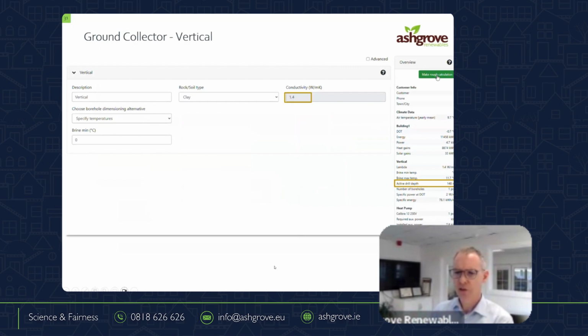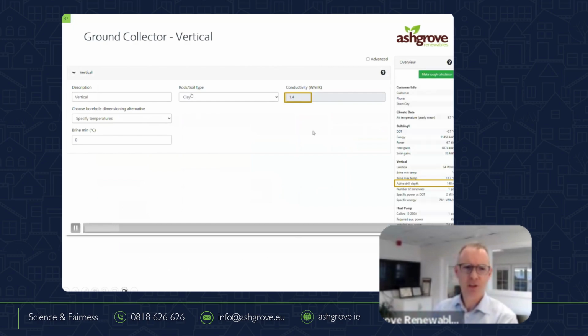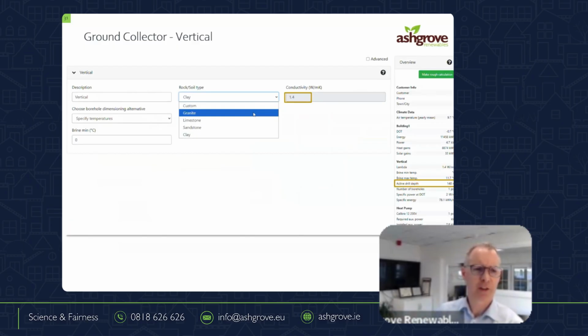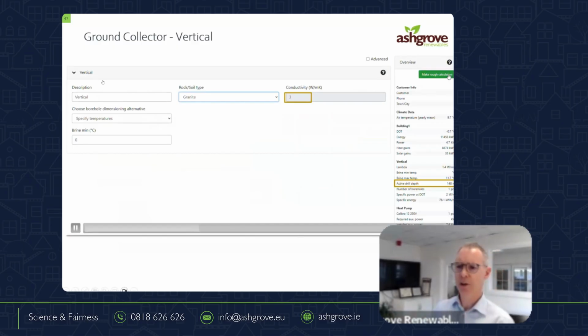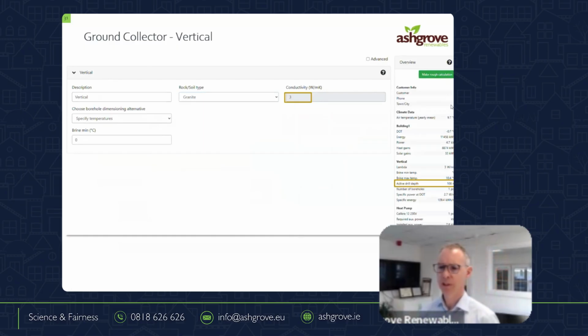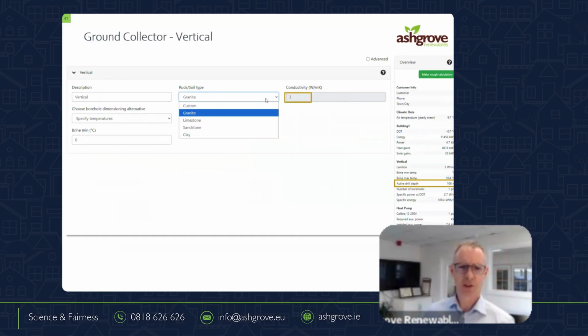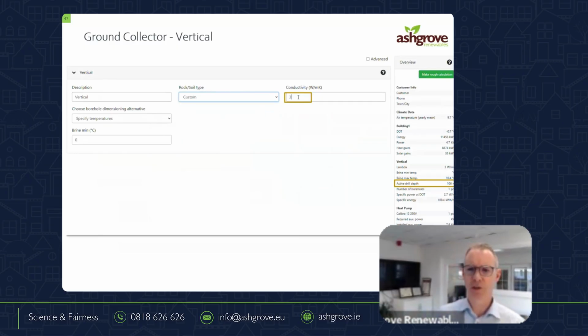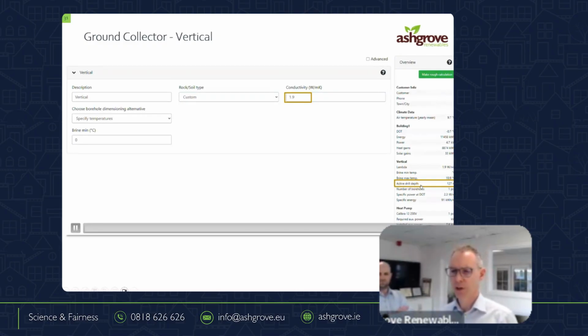Our software, this is just a screenshot out of it. You can see here, if we're taking energy out of, in this case, what have we chosen, Johnny? Granite. So this is a vertical borehole. It doesn't matter what we're taking out, whether we're taking out 10,000 kilowatt hours or 10 million kilowatt hours, the philosophies apply. We're going back to custom, we're changing the conductivity. So maybe if we know the conductivity, whereas if we just knew it was granite or whatever, we would choose granite. But you can see down here on the bottom, you can see here the active drill depth.